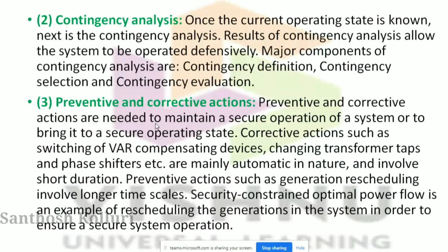Okay, so corrective actions such as switching of VAR compensating devices, changing the transformer taps, phase shifters are mainly automatic in nature. Automatically they are done by using automatic voltage regulators, AVRs. If there is a shortage of reactive power, then what happens? The generator automatically improves its excitation, and then it is going to meet the demand of reactive power. Then changing of the transformer taps: if the output voltage has been reduced or increased, then the transformer will automatically change its tapping position. Phase shifters or phase advancers improve the power factor and all. So these are the corrective actions nowadays. It has been taken in an automatic manner. Okay. Did all of you understand? I think.